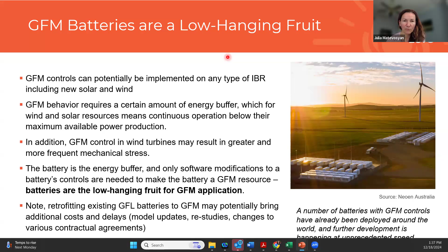You might think, if it's so easy to convert to grid forming, why not continue building them as grid following and convert later? But retrofitting is always difficult because there can be contractual agreements that pose limitations. You will need additional costs for restudies, and you will need to take them out of operation, during which time they'll lose revenue when changing these controls.